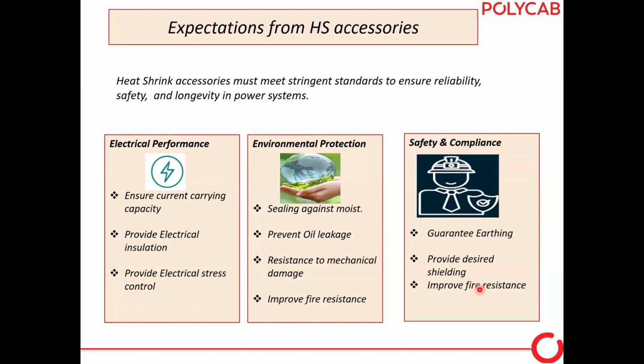So let's see what you are expecting from heat shrink accessories. Actually, I categorize these in three categories. One, any cable accessory has to provide electrical performance. It should ensure current carrying capacity, like cables do. Electrical insulation has to be given, and it must provide electrical stress control. So electrical performance has to be delivered by the cable accessories. Then environmental sealing: electrical performance is the basic thing, but there is also environmental protection, because water should not get in at that point, and if oil is there, oil leakage should not happen. Resistance to mechanical damage, and the third one is safety and compliance. So these three things have to be covered by the cable accessories. These are the basic things any cable manufacturer has to give.